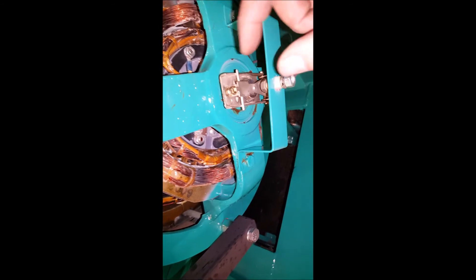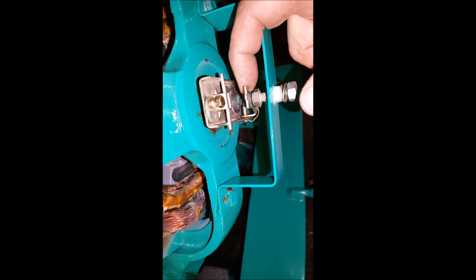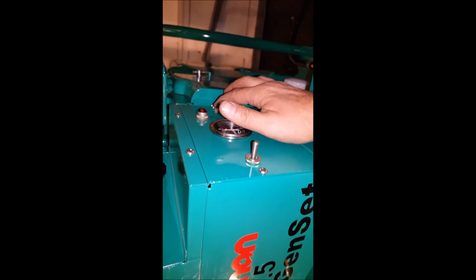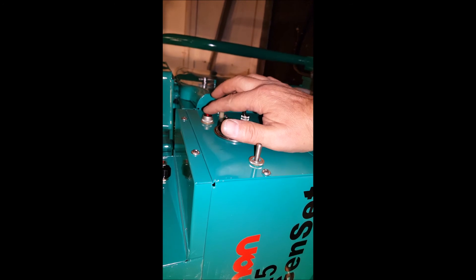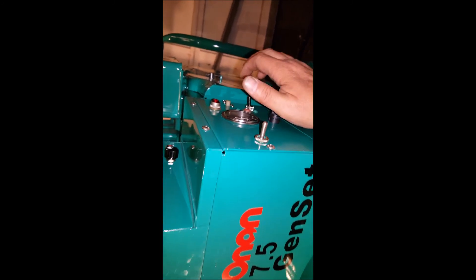That's really about it. For me, I'm going to adjust this thing so that if I do overspeed, once the generator comes to a stop this will reset — I don't have to remove the bell-end cover. All I have to do is hit this reset button. There's actually a coil behind this switch and it will cause the thing to pop out, the red light goes on, and you will not be able to restart this generator until you manually press this button.